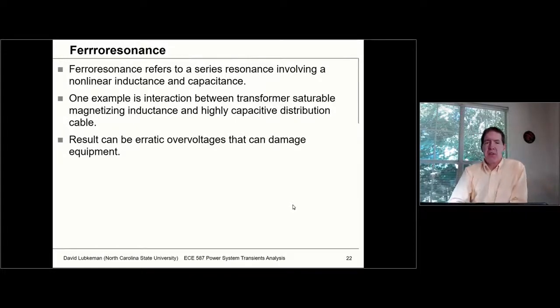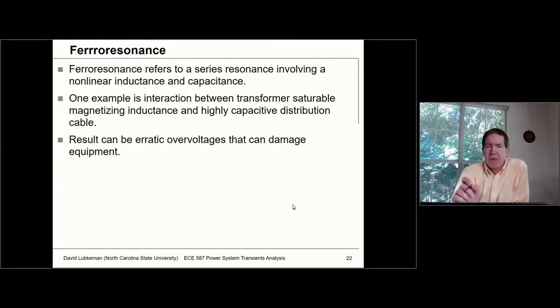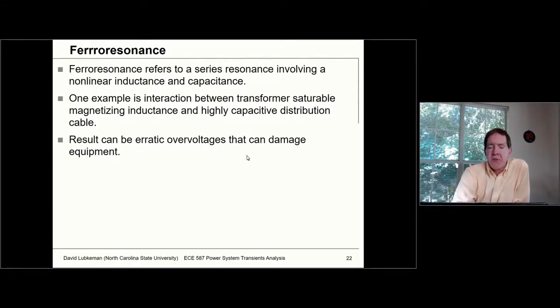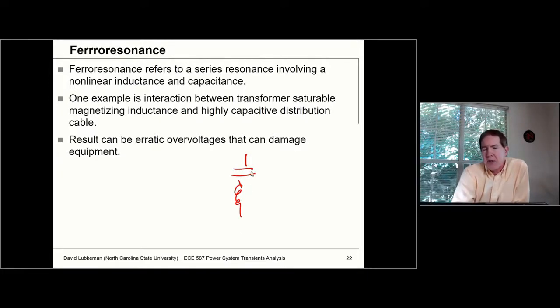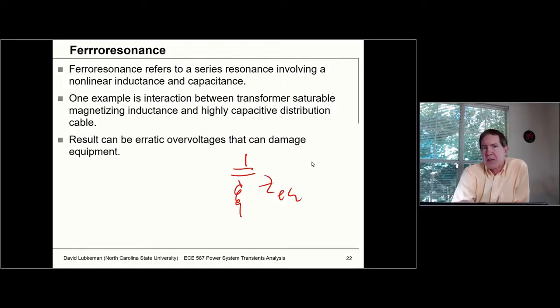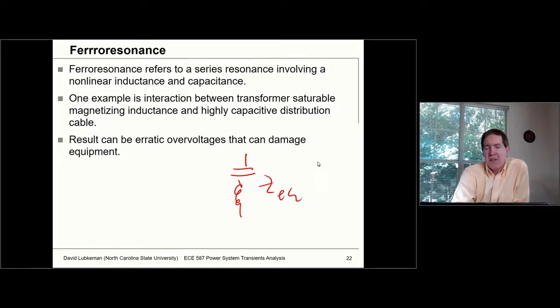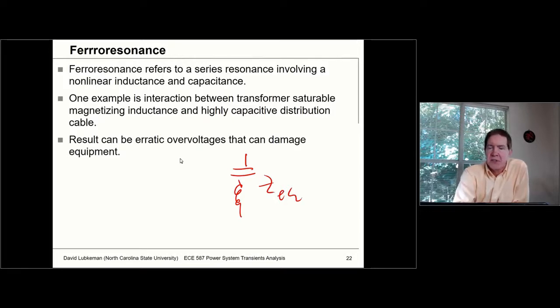Another nonlinear phenomenon is what we refer to as ferroresonance. This is due to the fact that if we have capacitance and inductance in series, there's going to be a frequency where this equivalent impedance goes to zero. That's going to result in high currents and also high voltages in the circuit. What complicates this is the nonlinear B-to-H relationship, because this gives us a nonlinear inductance as well.